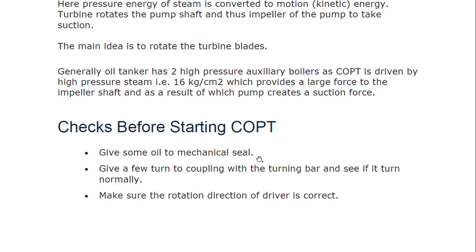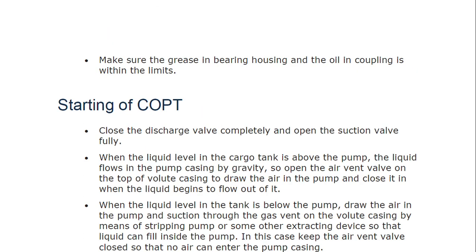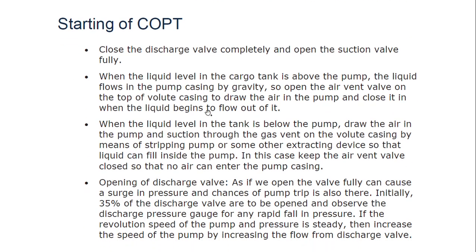The checks before starting COPT are very important from an operational and examination point of view. Give some oil to the mechanical seal. Give a few turns to the coupling with a turning bar and see if it turns normally. Make sure the rotation direction of the driver is correct. Also make sure the grease in the bearing housing and the oil in the coupling are within limits.